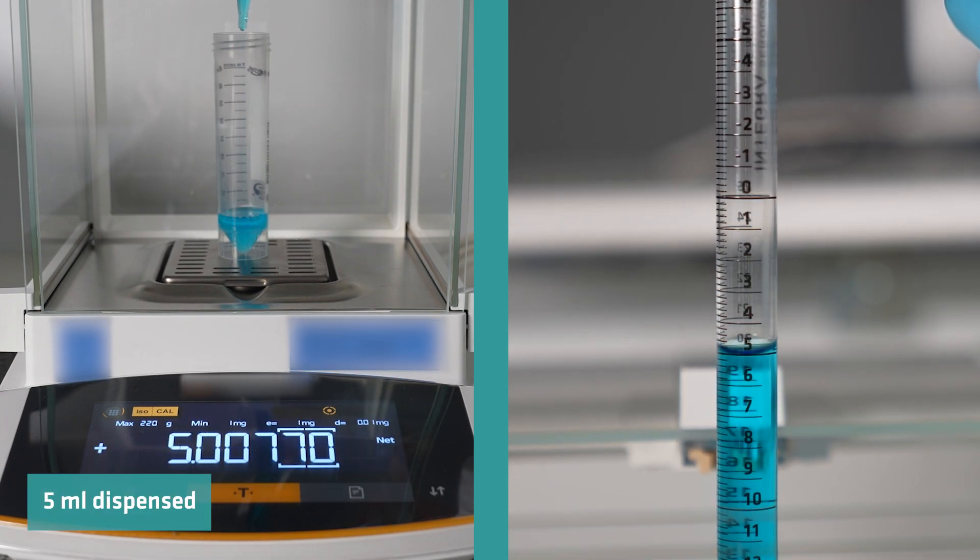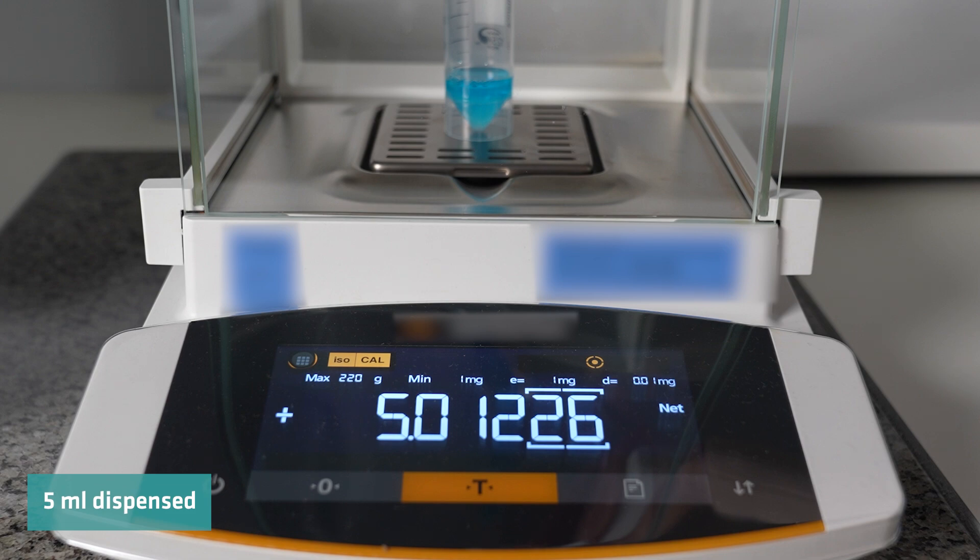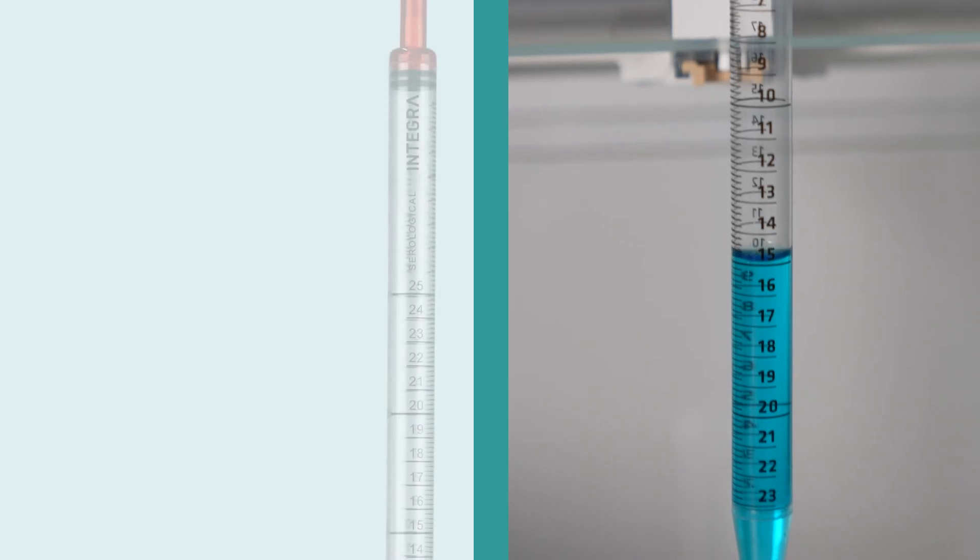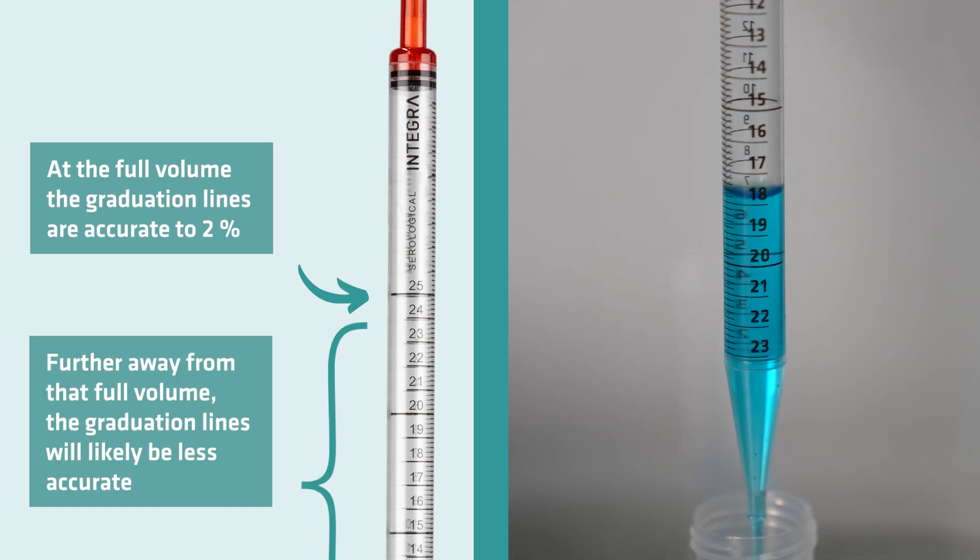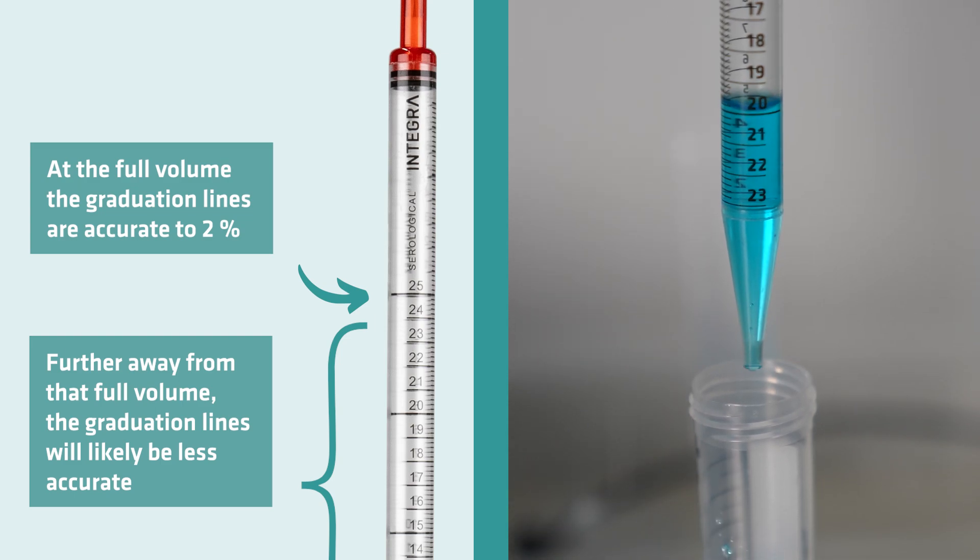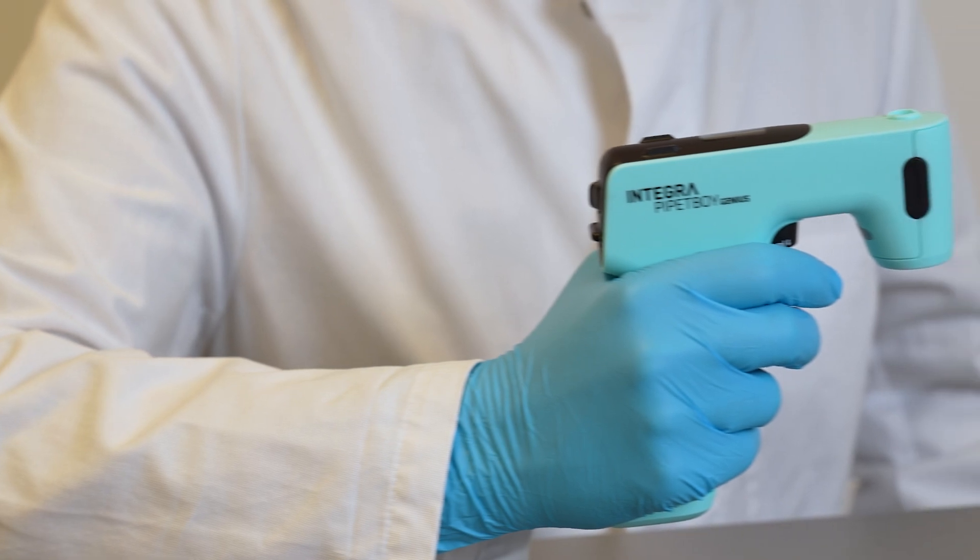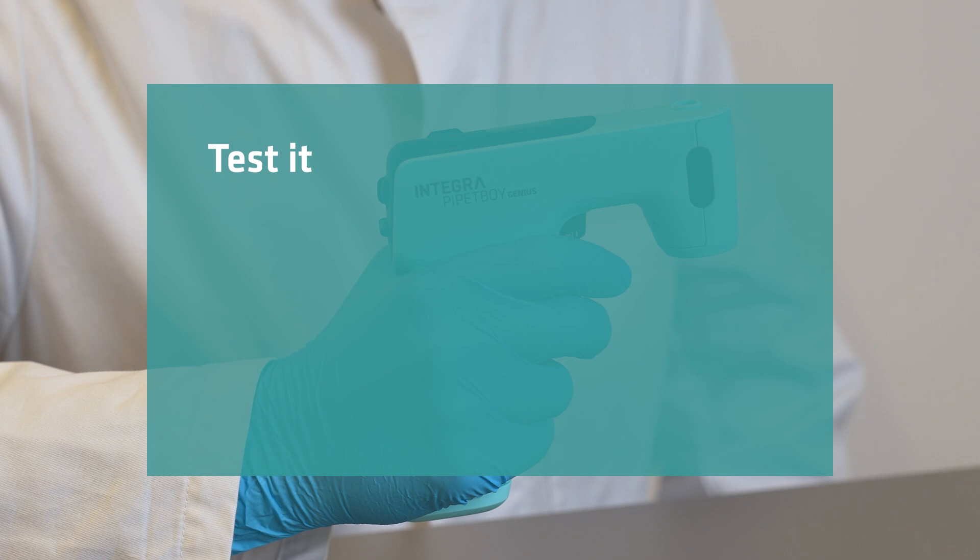That's likely much better than you're doing by hand. If you dispense multiple times, you'll get further and further away from where you think the liquid should match the graduation, but again, each dispense is within 2% of where it should be. There's something else: the graduation lines on serological pipettes are very accurate at the full volume of that pipette, but further away from that full volume, the graduation lines will likely not be 100% accurate. This is true with all serological pipettes. So trust your Pipetboy Genius—it's accurate. In fact, test it if you're still skeptical. Use a balance or simply your eyes.